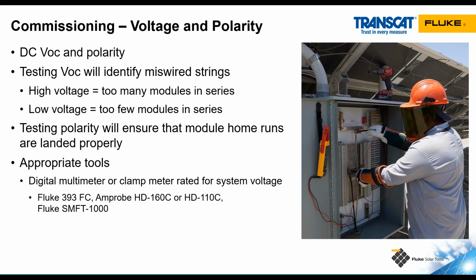The two AmProbe models that are listed on the slide are actually being discontinued because we are going to be releasing a Fluke 1500 volt category 3 rated multimeter, the 283. That will be coming out very shortly in the third quarter. That is capable of testing up to 1,500 volts, has the same polarity feature that the 393 has. It is also capable of testing AC voltage in category 4 environments up to 1,000 volts.